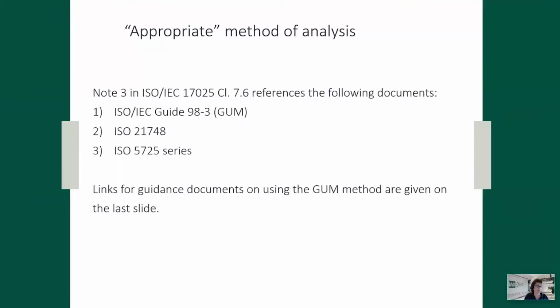In this presentation, we don't have time to focus on numbers 2 and 3. We concentrate on the GUM because for accredited calibration laboratories, in addition to ISO IEC 17025, laboratories also have to abide by the policies of ILAC, and one of the relevant policies is ILAC P14. That document states that the measurement uncertainties for calibration laboratories should be computed in accordance with the GUM. So that's what we're concentrating on here.